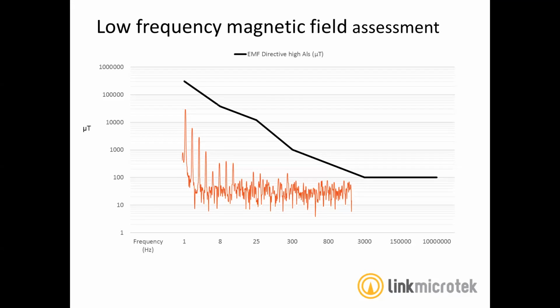I often get questions about the weighted peak method, and it sounds a bit complicated, but really, behind the scenes, the instrument is just weighting all of the peaks of the harmonic noise against the action level. Can you imagine how tedious that is to do manually? You have to put a value against each peak, then weight that value against the action level, and then add all those up. The beauty here is that the instrument detects that and does it all for you automatically. So you just get a single total value in terms of percentage of the action level.